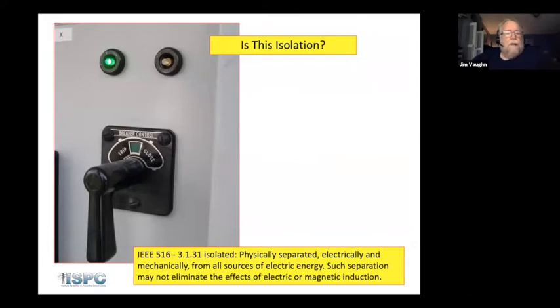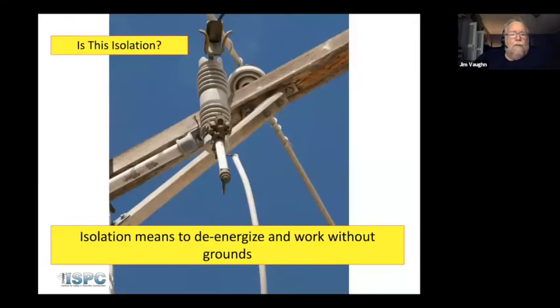Now, isolation is opening a breaker. If we open switches on either side of the bus that we're working on, we have physically separated that bus away from the source of feed. And if we have control over those switches, we consider that isolation. If there's a possibility that that circuit could become energized, that's when we ground, or we work it as if it is energized, even though it is isolated by switches. There's a very big gray line between isolation and insulation, because you may have both work techniques being used at the same time wherever you're at.